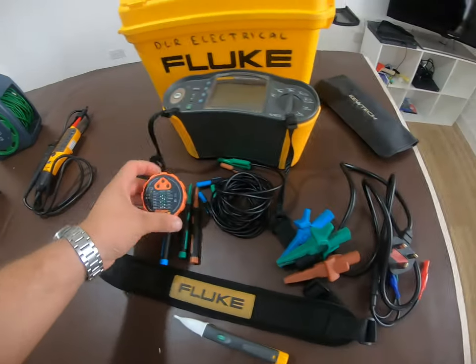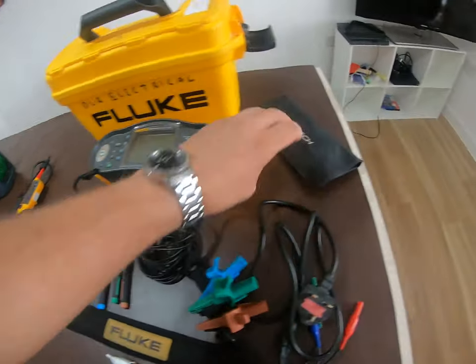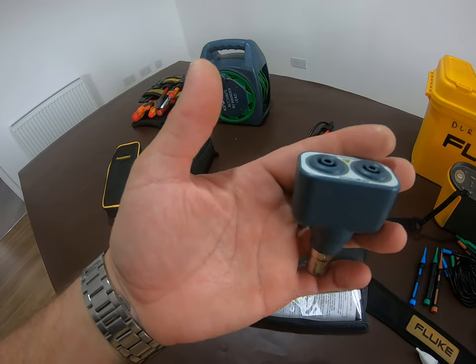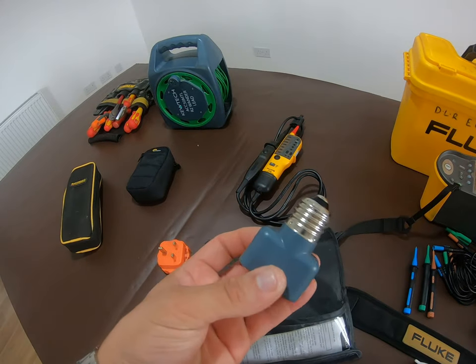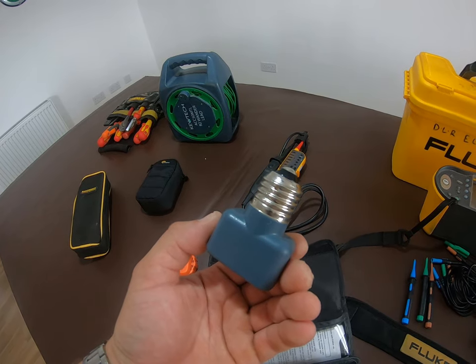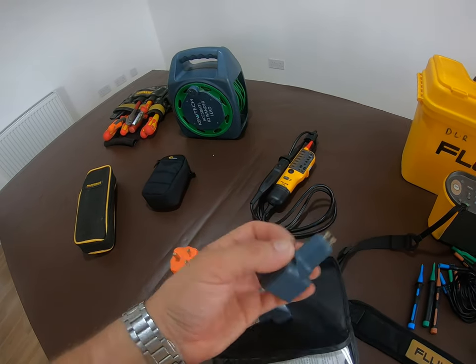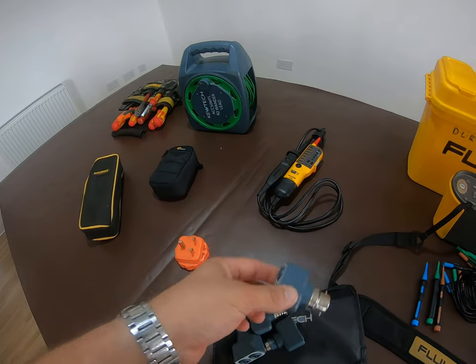I also have a voltage tester, a little polarity checker for socket outlets, and for awkward light fittings I've got these Kewtech Lightmate adapters. These are great for avoiding taking down things like chandeliers and awkward lights you don't want to disturb. You put your earth feed on the metal frame, then plug these into the lamp holder and you've got access to the live and neutral to do your test.